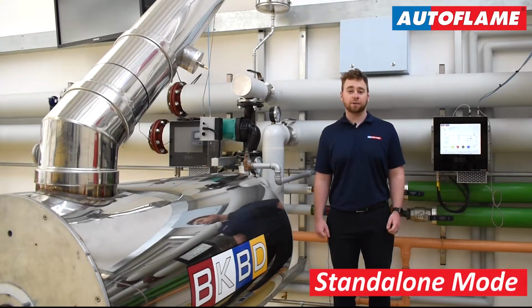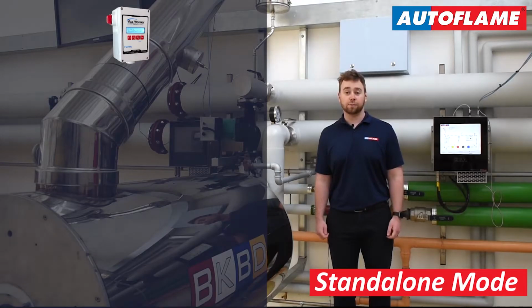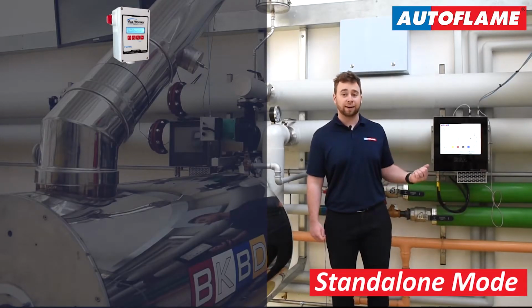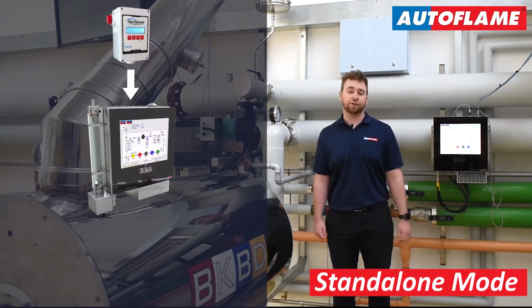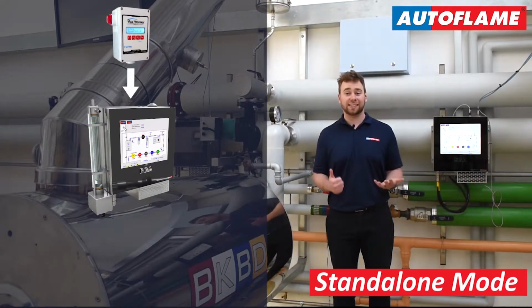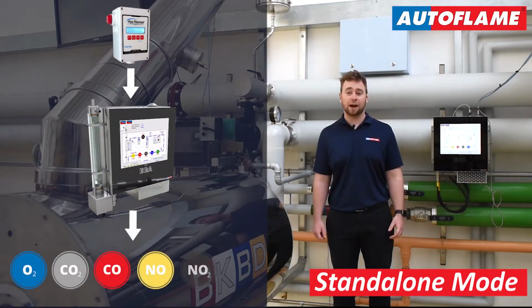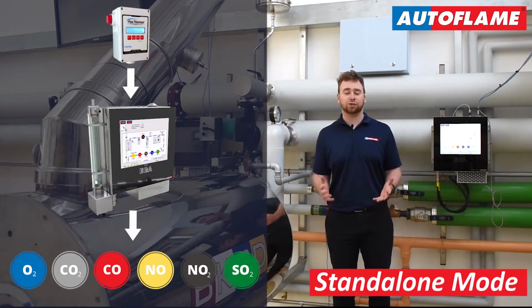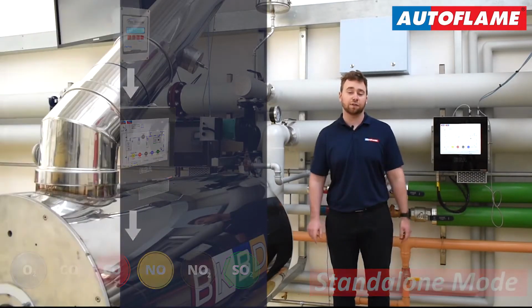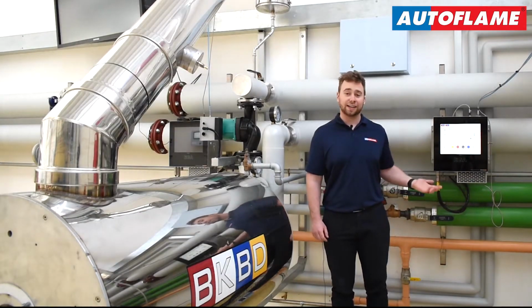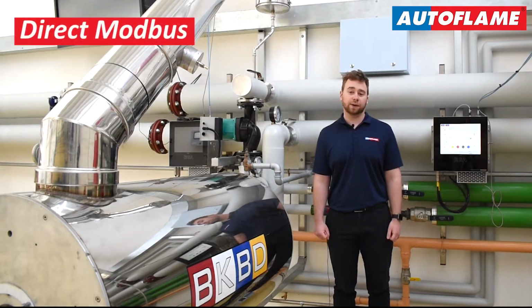In standalone mode, a 4 to 20 mA input from a fuel flow meter can be wired directly into an EGA for more accurate fuel usage. There are also 6 dedicated 4 to 20 mA outputs from the EGA, which allows extraction of certain parameters such as emissions levels, temperatures and so forth. Now, the EGA Evo now has direct Modbus.